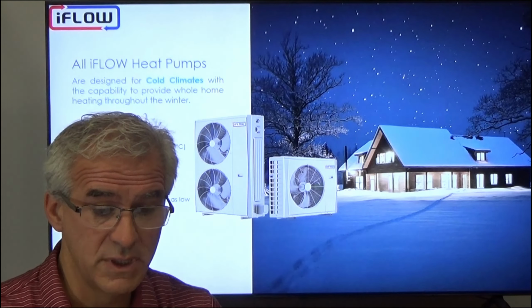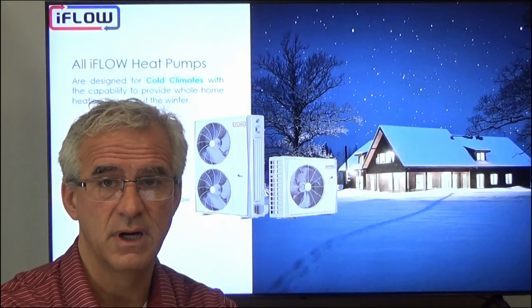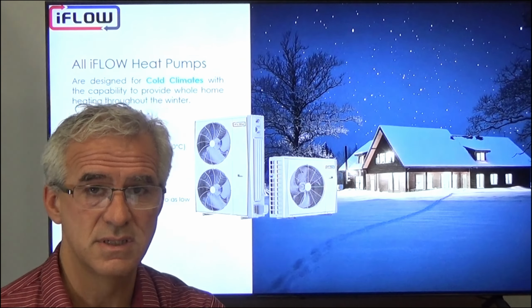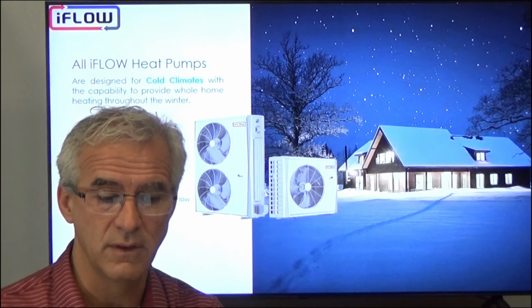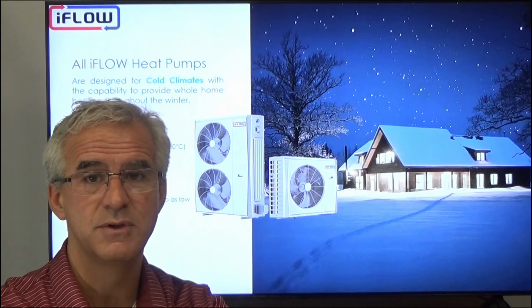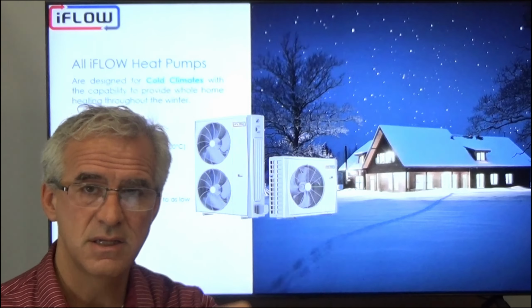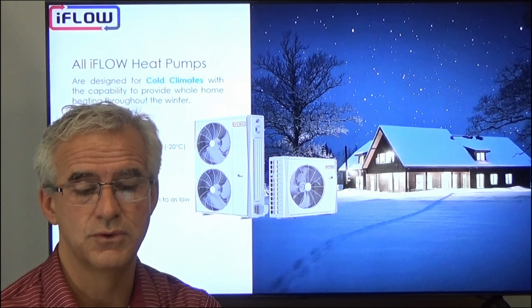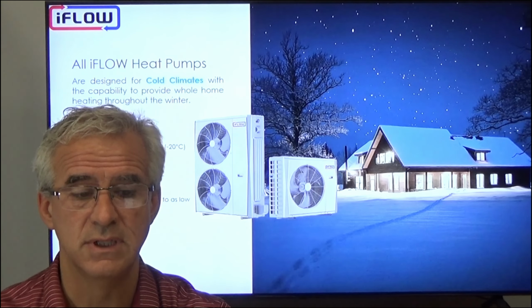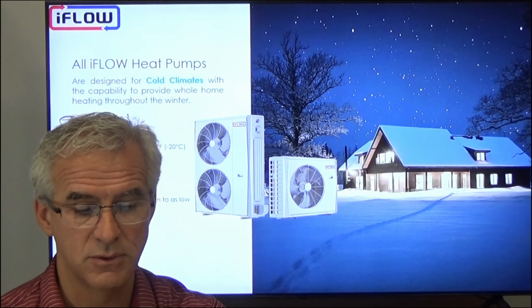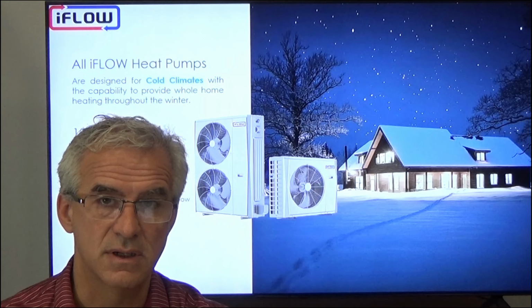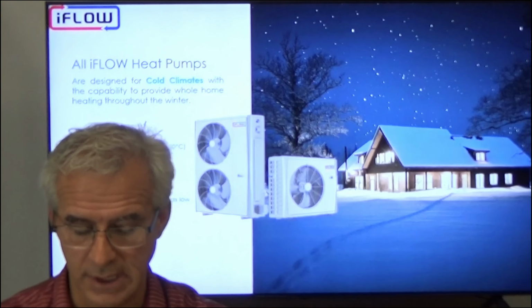Even though we guarantee delivery of 100% capacity at minus 20 Celsius, that doesn't mean we stop operating there. We will still operate down to minus 30. The delivery capacity will drop off, but nonetheless we'll still be able to deliver heat into your home down to as low as minus 30 Celsius, which is minus 22 Fahrenheit.